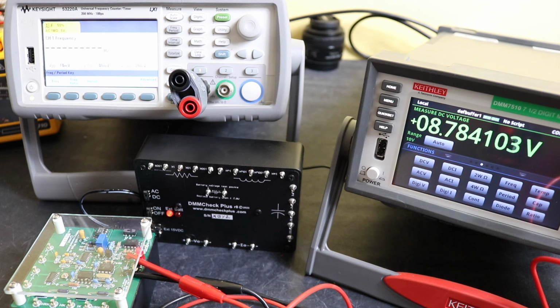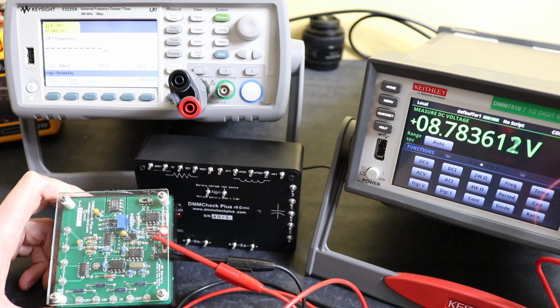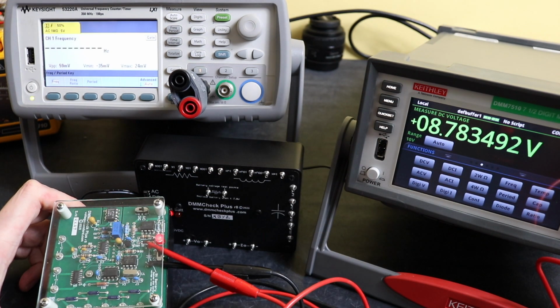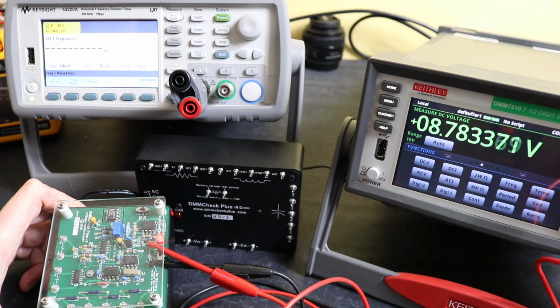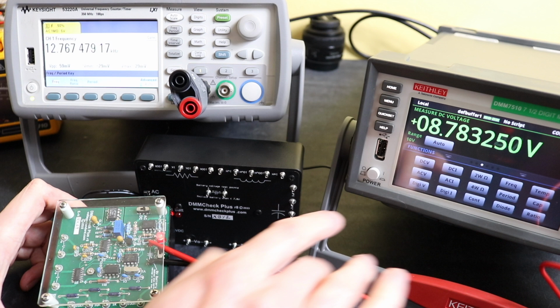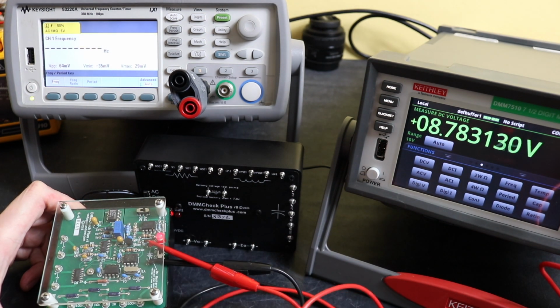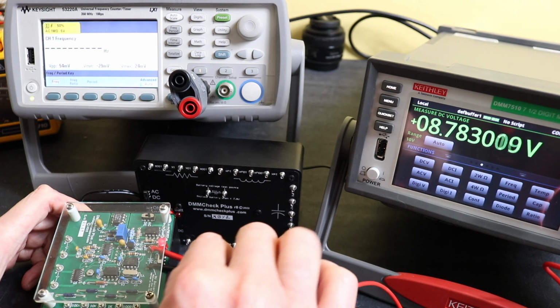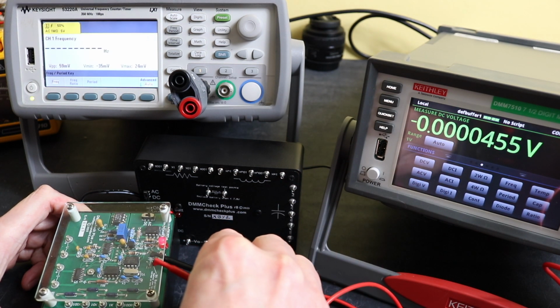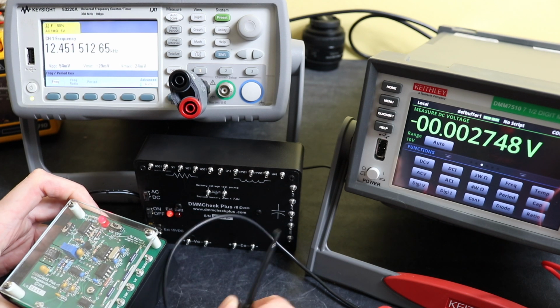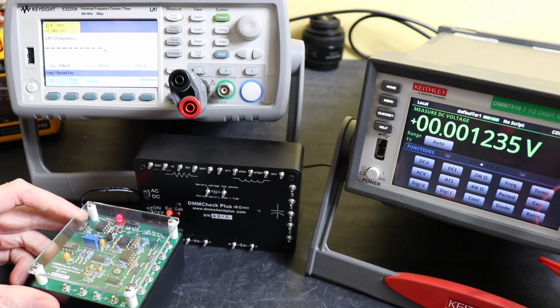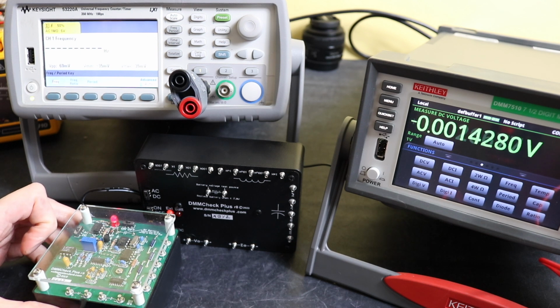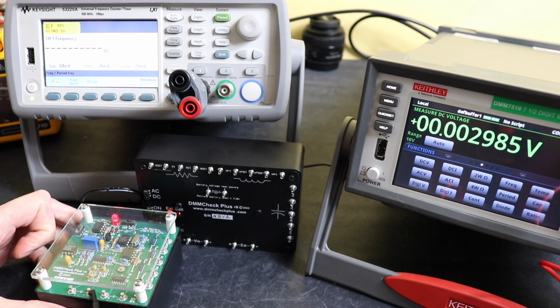Okay, so we are set up to make our readings on both of these DMMCheck Plus units. I will just cut through the video just so you see the actual values. We're starting off with revision 5, the old one down here, and I'm just verifying the battery voltage on there is currently 8.78 volts, so we are above the recommended value on that. I have run auto cal on these, and these instruments have been warming up for just over an hour now. It did come back to say it was ready for auto cal, so it should be all good to go. We are on DC volts to go to first. Put our little instrument there.